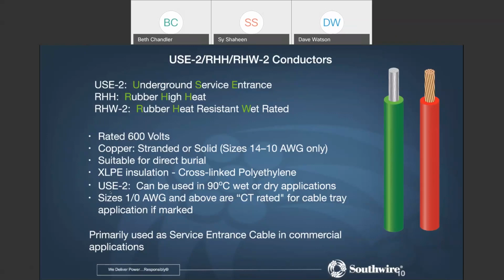So this product, however, does have the necessary flame retardancy and the recognition by the NEC that it can be used internally within raceways, just like the XHHW or THHN conductors. And in addition, it can be used outdoors and direct buried as a USE underground service entrance product.